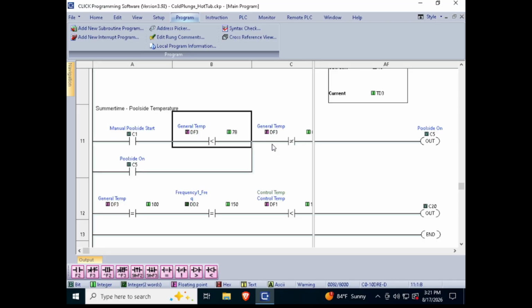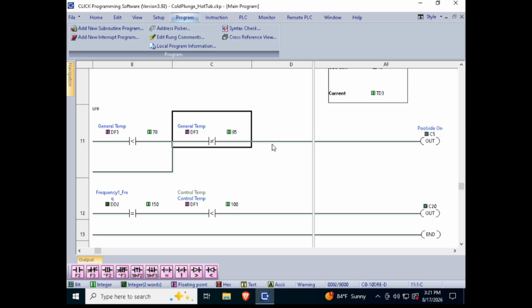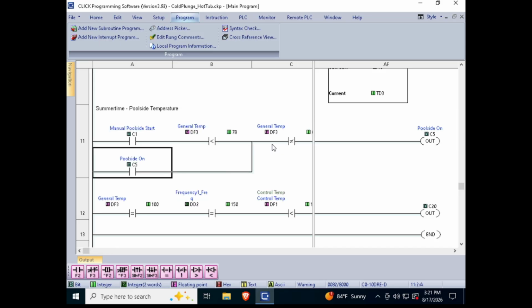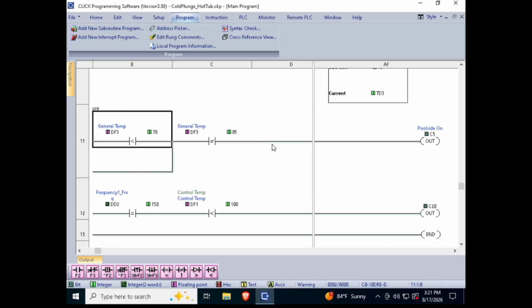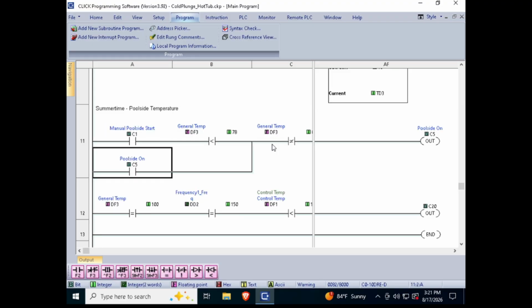It's going to be below 78, so that's true, and it's not going to be 85, so that's also true. Then this poolside bit is going to turn on, which in return latches in C5 right here, since they're both referencing the same bit. That latches in, and then it's going to dodge the less-than general temp condition, so this will constantly be on and it'll just keep heating up.